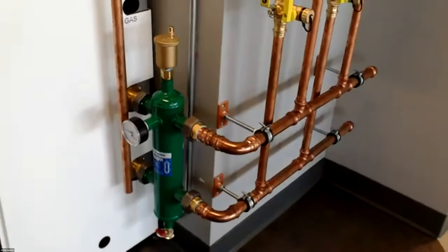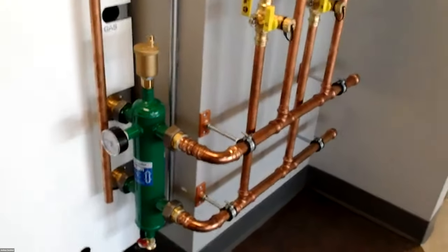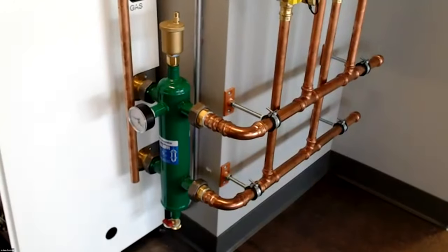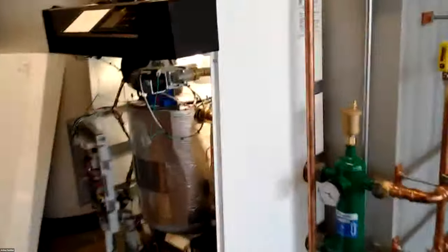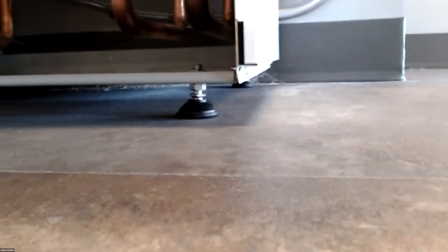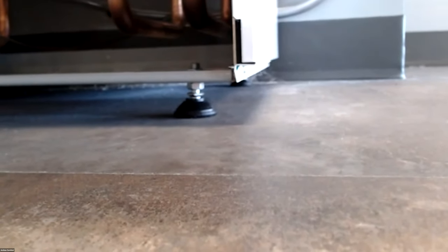So that's a beautiful low loss header. Yeah, I like the green. The green's nice. Love the Caleffi. Yep. So real easy. Simple install. Put it on the floor. The feet too. As you can see, they're rubber and they are leveling feet. So if you need to level off the boiler, you 100% can do that.